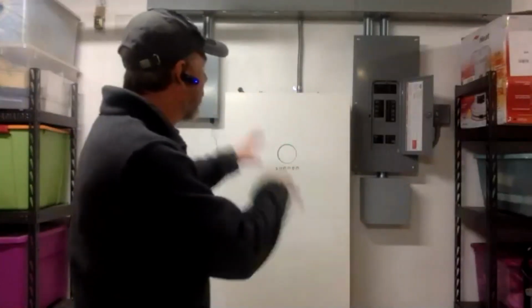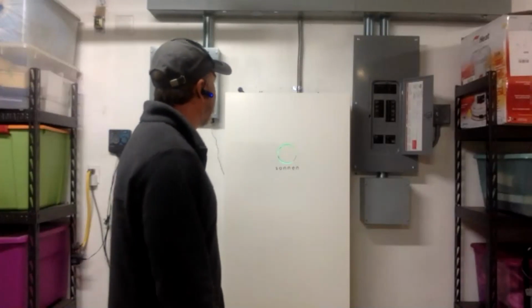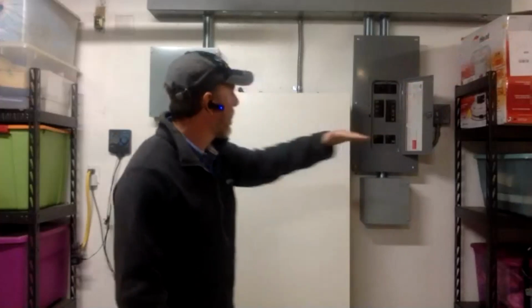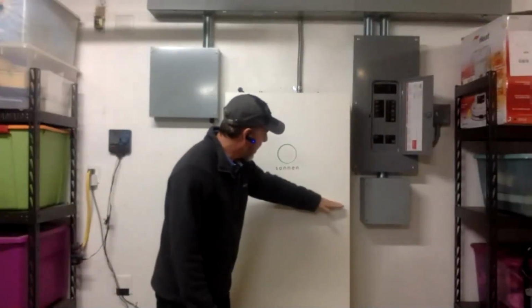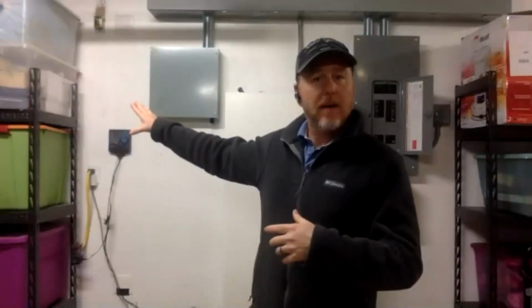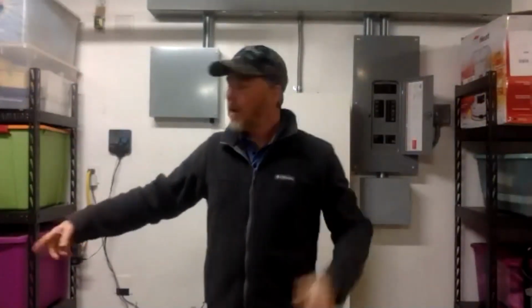As far as the mechanical part of this, it's really easy. There's a frame behind here - you put the shelves on, you mount the frame. Typically you're going to use a piece of unistrut that goes behind here, about right here and right here, and bolt the frame on. Then you put the batteries in there and wire them up. You bring the AC in from the main panel and from your protected load panel - line 1, line 2, neutral, equipment ground - separately into our unit. Then you bring in Ethernet, and that's it.